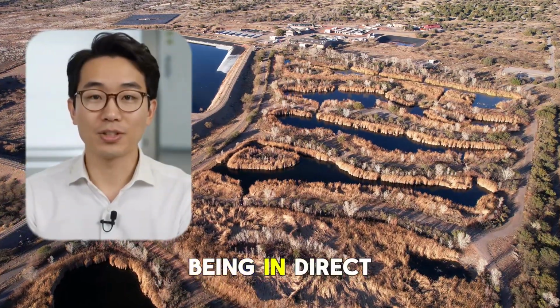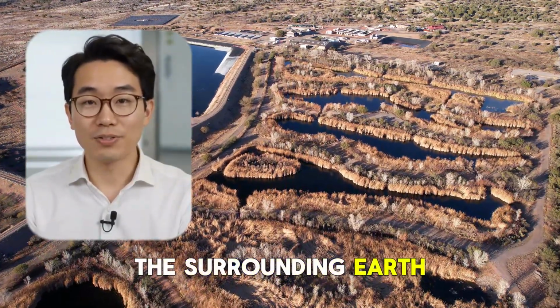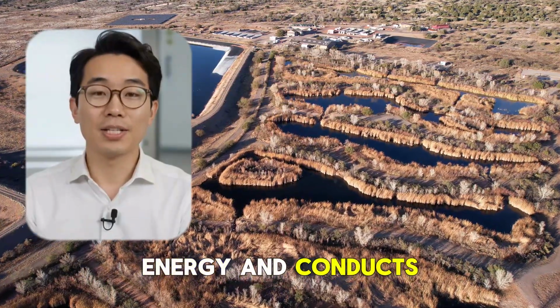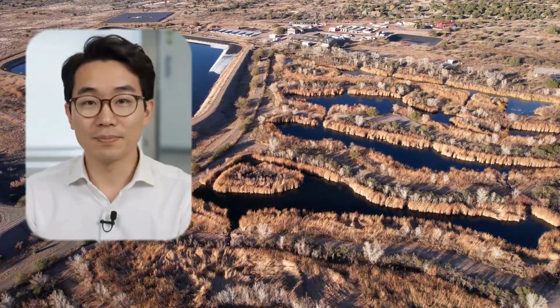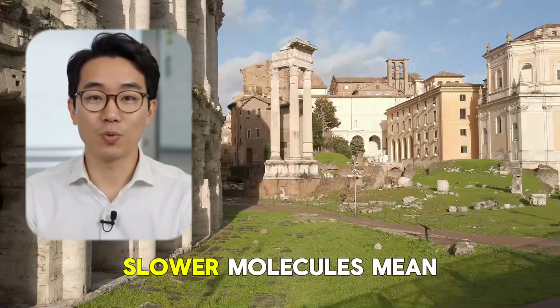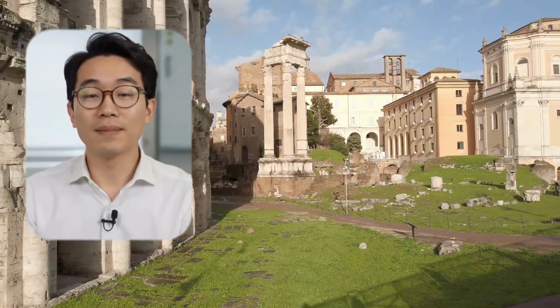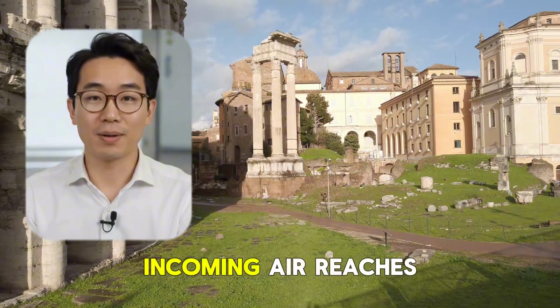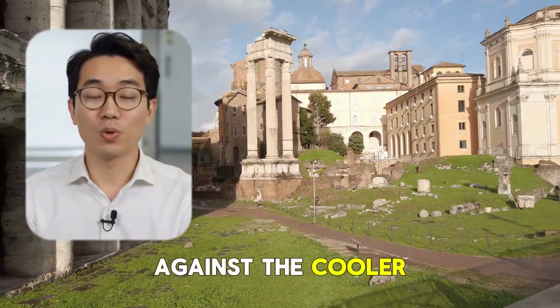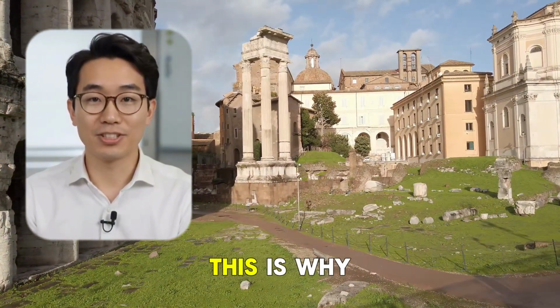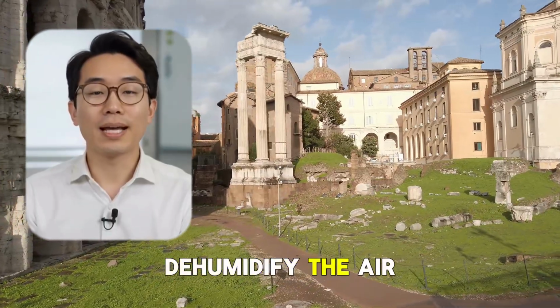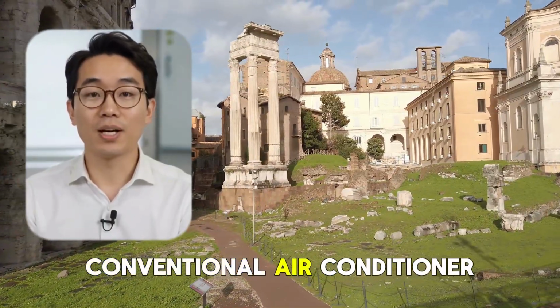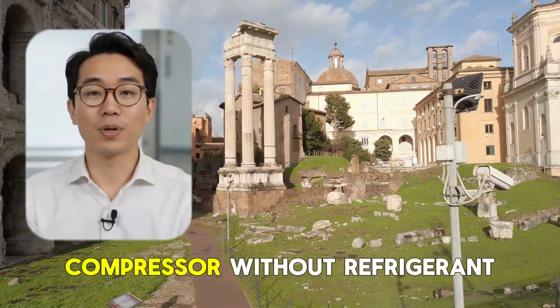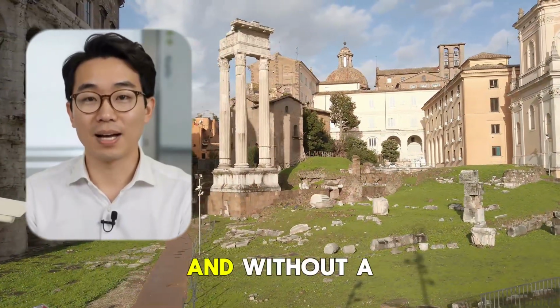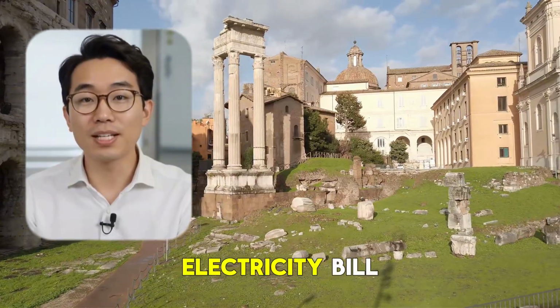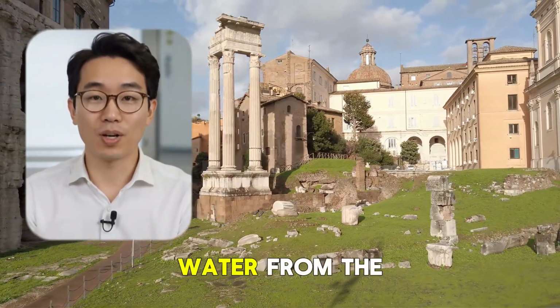The pipe wall, being in direct thermal contact with the surrounding earth, absorbs that kinetic energy and conducts it outward into the soil mass. The air molecules slow down. Slower molecules mean lower temperature. Simultaneously, moisture in the warm incoming air reaches its dew point against the cooler pipe wall and condenses out. This is why earth tubes also dehumidify the air, exactly like a conventional air conditioner does, but without a compressor, without refrigerant gas, and without a $150 per month electricity bill. Earth tubes remove water from the air.